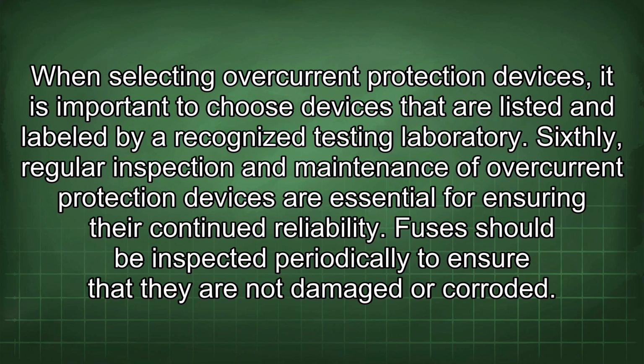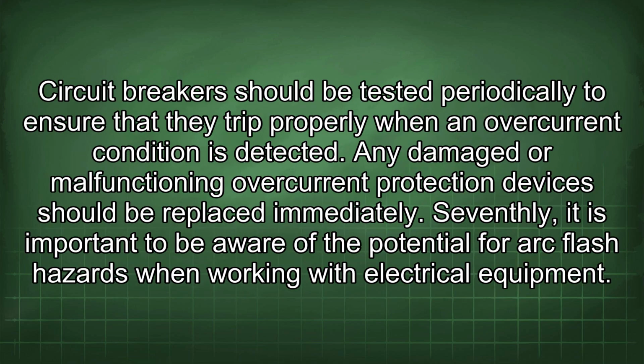Sixthly, regular inspection and maintenance of overcurrent protection devices are essential for ensuring their continued reliability. These should be inspected periodically to ensure that they are not damaged or corroded. Circuit breakers should be tested periodically to ensure that they trip properly when an overcurrent condition is detected. Any damaged or malfunctioning overcurrent protection devices should be replaced immediately.